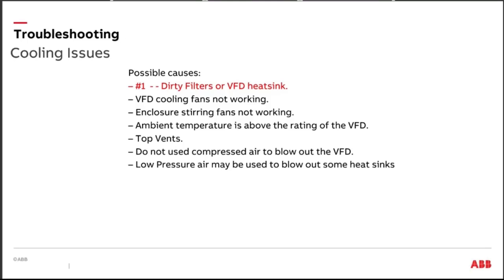Okay, but along with that filter kit, we need education and maintenance. We need to know that that filter is there for a purpose. It's there to get dirty. It's there so that we don't pass that mess inside the drive cabinet. But once that filter starts doing its job, it becomes blocked. And we need to know that we're pulling that filter out, or we're testing that filter, on a religious basis.